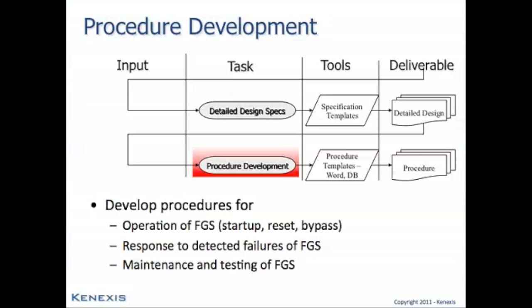Also, maintenance procedures for the system need to be developed. Importantly, the response to detected failures needs to be developed and considered. If a component in an FGS system fails, it's important that the failure be detected quickly and repaired within the mean time to repair that was assumed during the design phase and was used as an assumption in the safety availability calculation. If the repair is not done within that time frame, the achieved safety availability and the overall tolerable risk levels of the facility might be violated by not repairing that device as scheduled and as assumed.